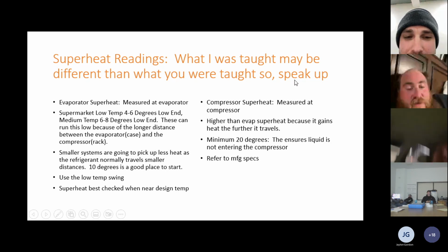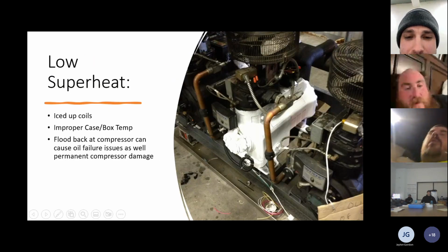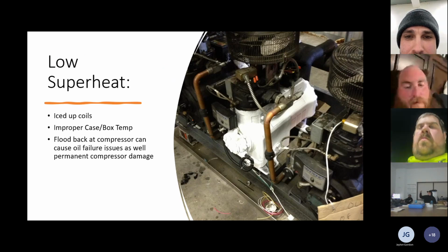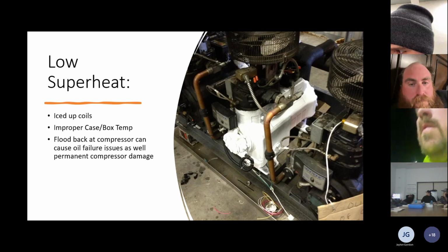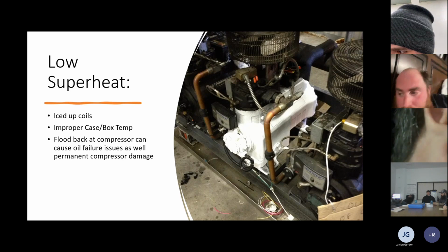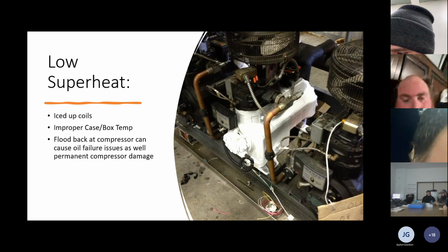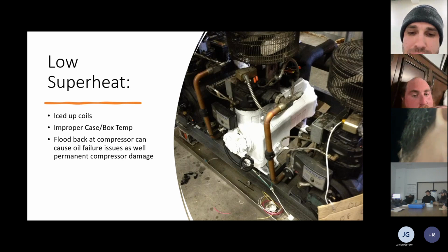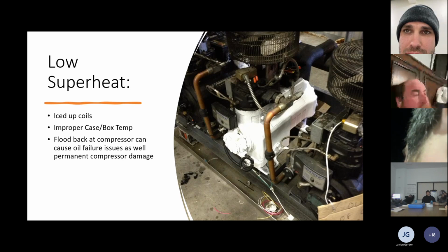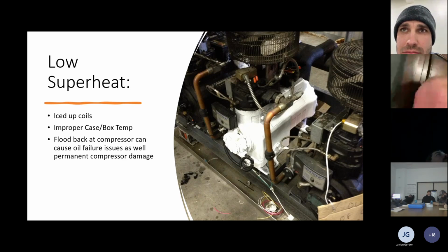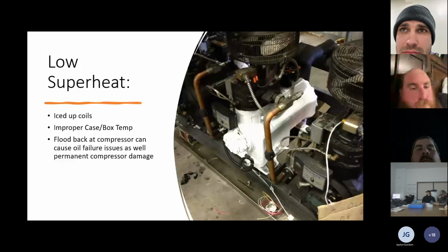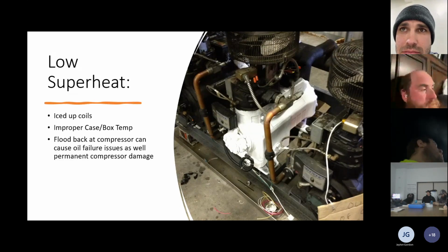Well, you could see the change too. So that's good data to document. But I do think that brings up a valid point for what Dylan's asking. Let's make sure that the equipment is clean, especially because we're probably talking about a walk-in cooler or walk-in freezer. Smaller systems, like Dustin said, are affected more; your larger scale stuff is not going to be affected as much. But first, verify that your evaporator coil is clean and your condenser is clean.